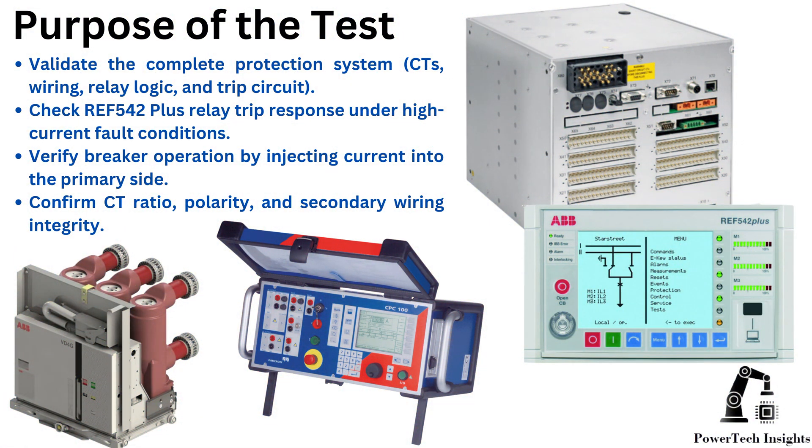Purpose of the test: Validate the complete protection system. Check REF542 Plus relay trip response under high current fault conditions. Verify breaker operation by injecting current into the primary side. Confirm CT ratio, polarity, and secondary wiring integrity.